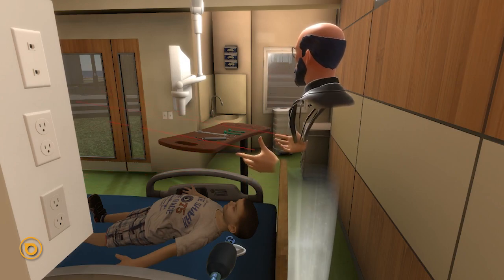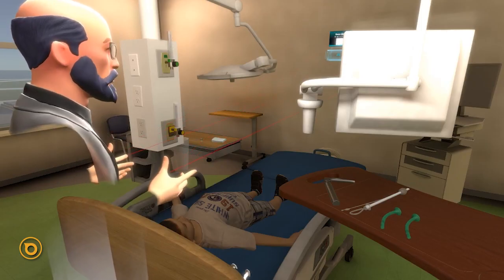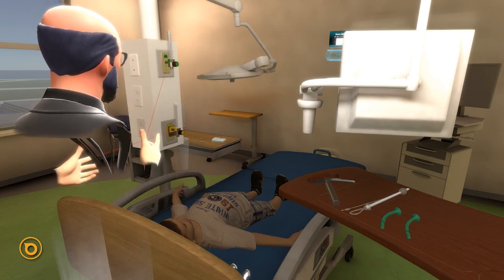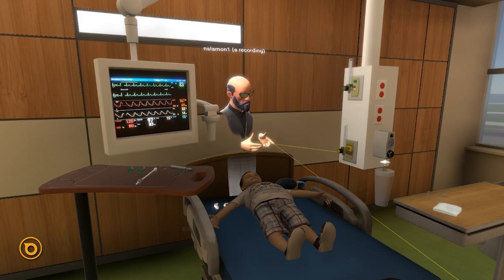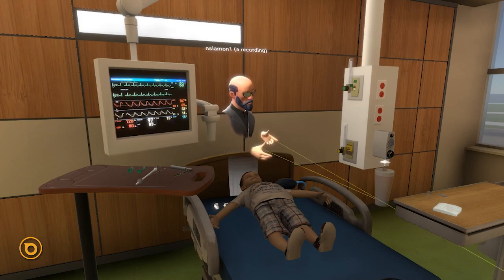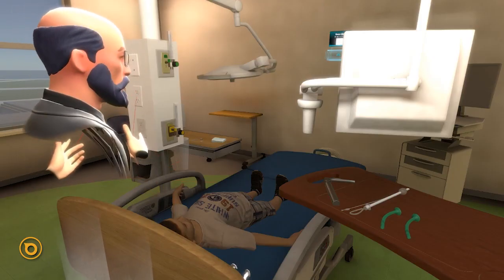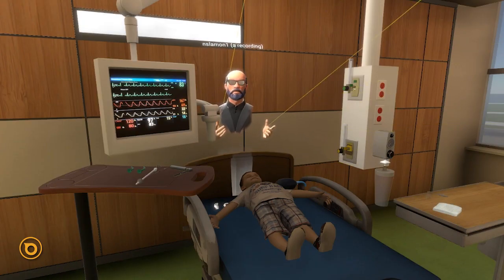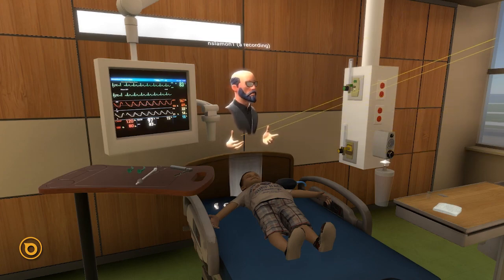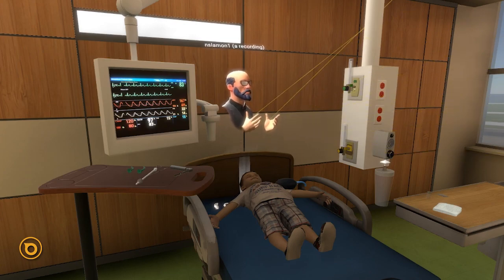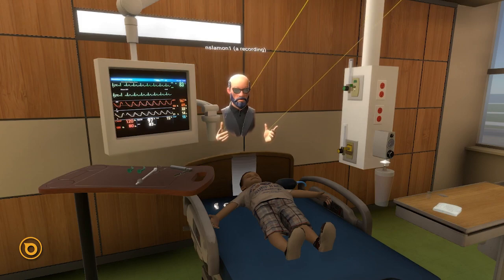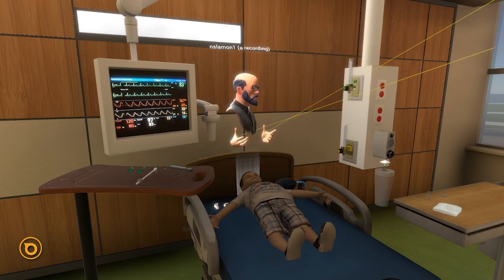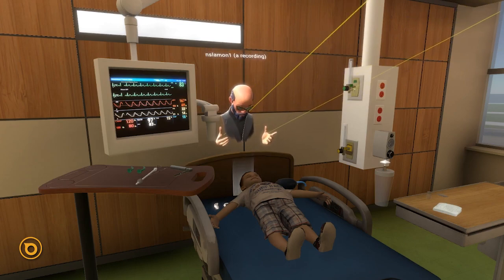Let's go over the room itself. This is a typical pediatric ICU. The things we're going to need are oxygen, medical air, suction, electrical outlets, a monitoring system, and equipment. This room is arranged with a boom system where all those different pieces are on a mobile boom that can be moved around the room. Others have all that equipment on a head wall — neither one is better or worse than the other, they're just different.